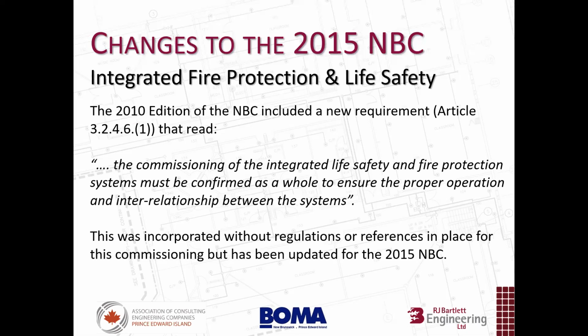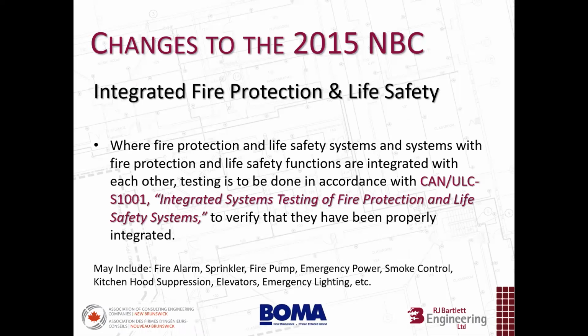But now in the 2015, we have some additional guidance here, and it's more clearly laid out. So we actually have reference to a standard, and I'll just read it out here: where fire protection and life safety systems and systems with fire protection and life safety functions are integrated with each other, testing is to be done in accordance with CAN/ULC-S1001, Integrated Systems Testing of Fire Protection and Life Safety Systems, to verify that they have been properly integrated. And then we have a list of examples on the bottom. So fire alarm and sprinkler, they're communicating back and forth all the time. In this instance, we also have verification processes that address a lot of the integrated communication between a fire alarm and sprinkler system, so there's not much work to be done in addition to these with respect to the integrated systems testing.